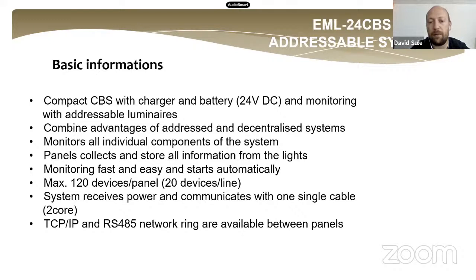The lights can run maintained and non-maintained. For the maintained lights, for example the exit lights, the maximum continuous power the panel can give is 10 amps. So 10 amps is the limit for the maintained lights, but the full capacity of the panel is 18 amps. This panel can be connected to the network with simple TCP/IP and RS-485 network communication.